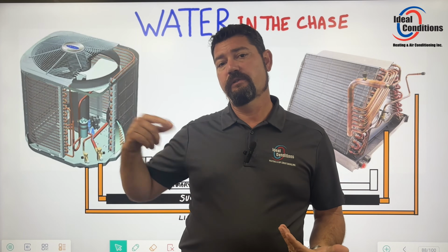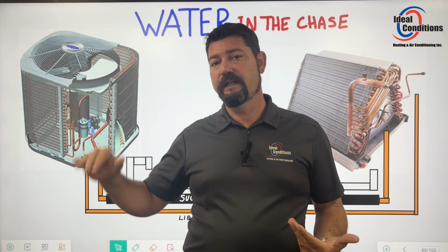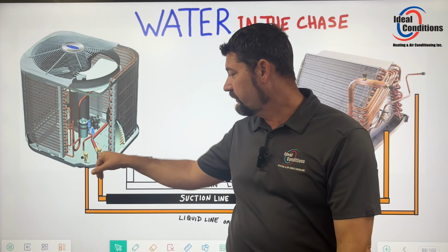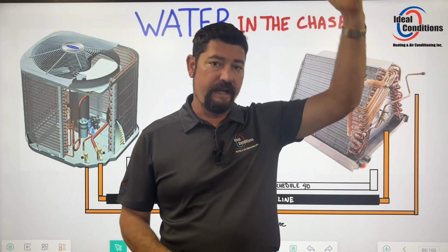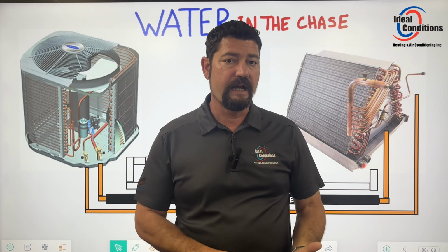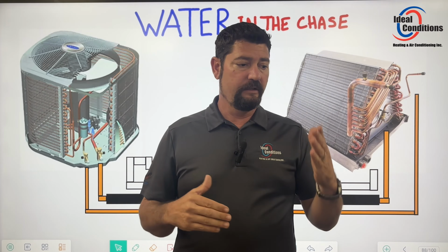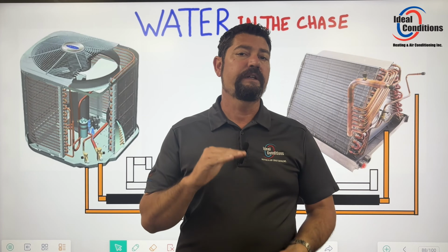You may flood out your evaporator coil with liquid refrigerant and bring it down to zero, and by the time it gets to the service valves outside, if it went across that hot attic and down the side of the building with high heat index and high ambient temperatures, it may be in the right superheat range.